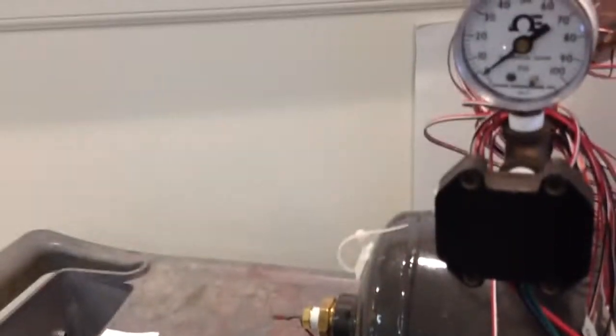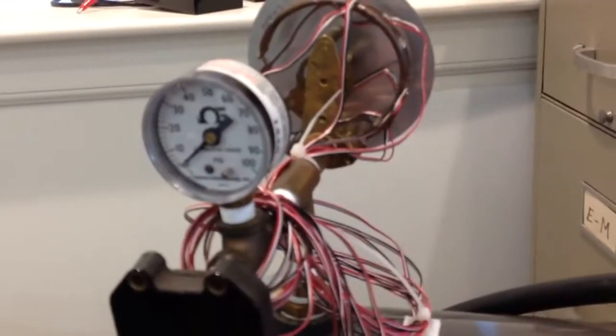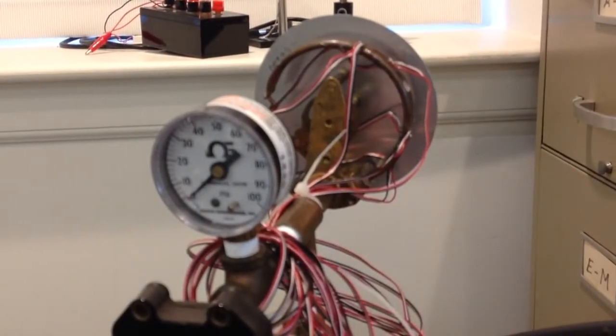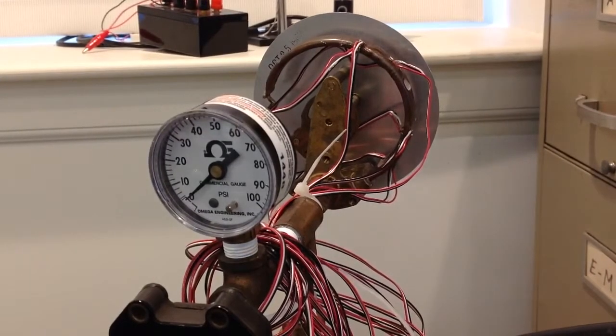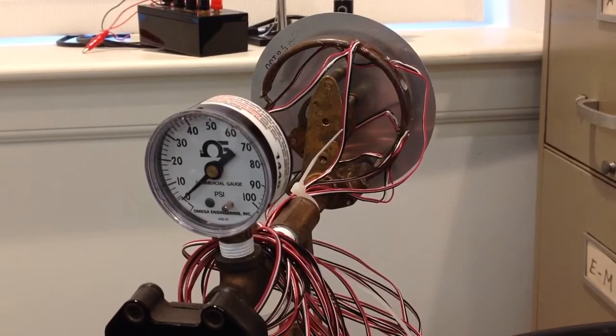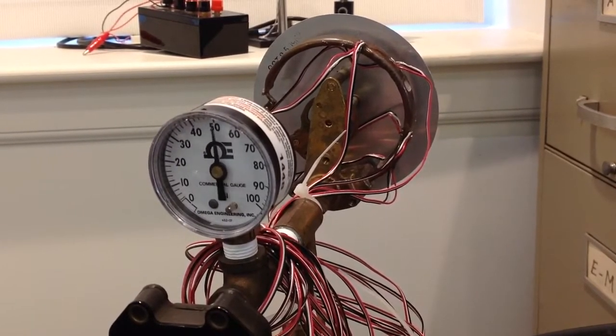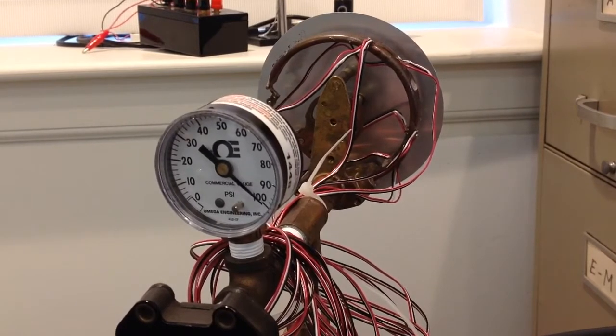So now I'm going to pressurize the tank, and I would like you to see how Bourdon tube is reacting to pressure. So right now we have 0 psi, but remember, 0 psi is not absolute vacuum. That is the gauge pressure. So we have the atmospheric pressure inside. So now we are pressurizing the chamber. See how the Bourdon tube deflected. And also have a look at the needle. It takes time to settle down, so you have to wait until the steady state while performing the calibration, okay?